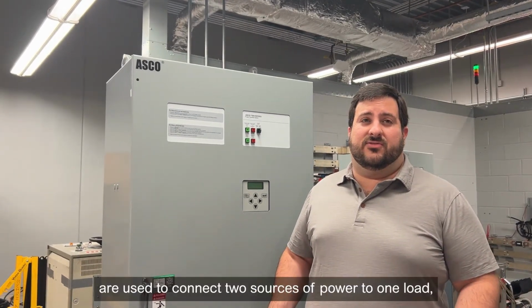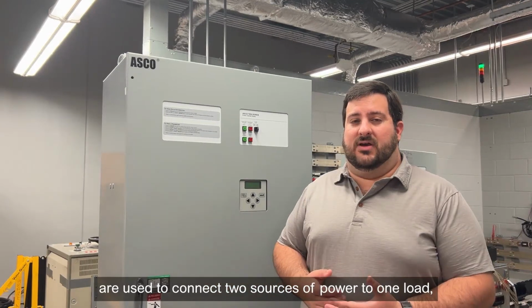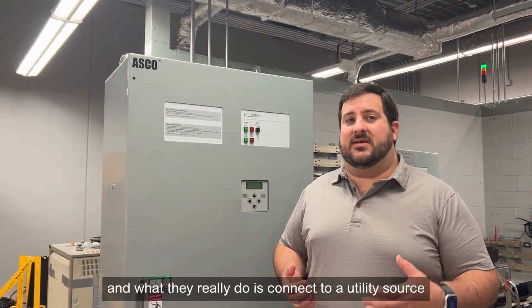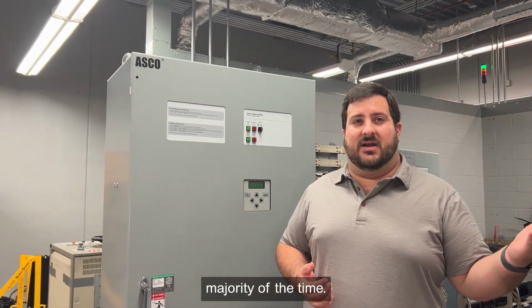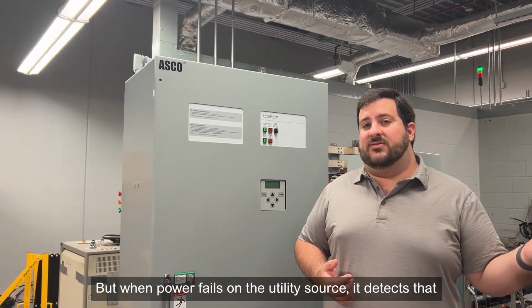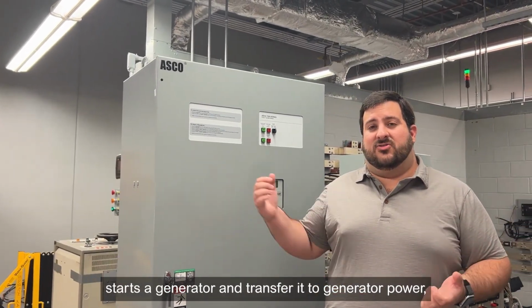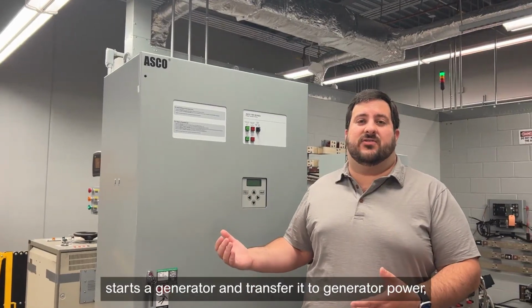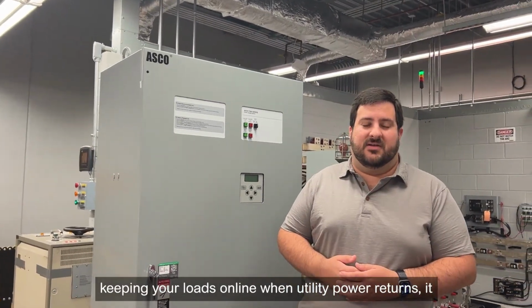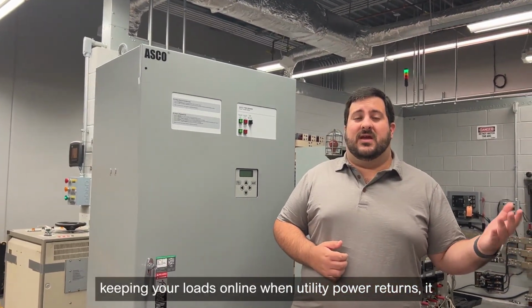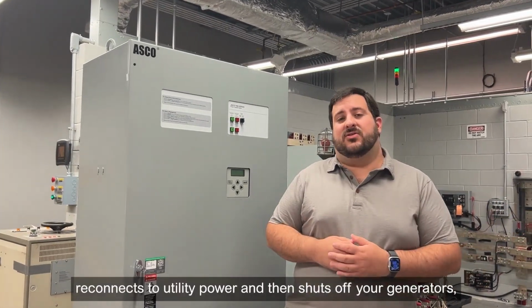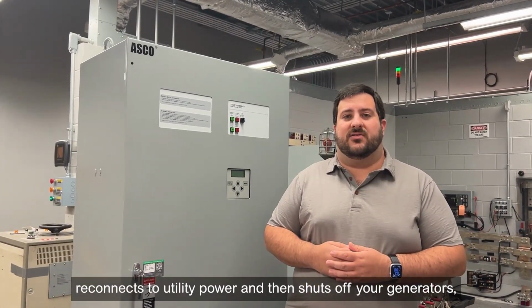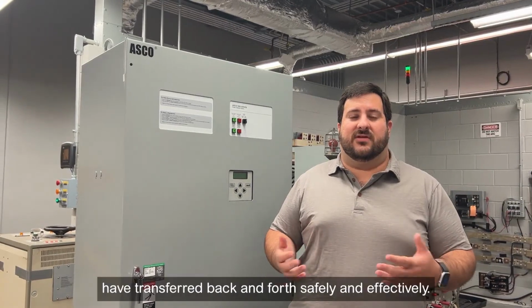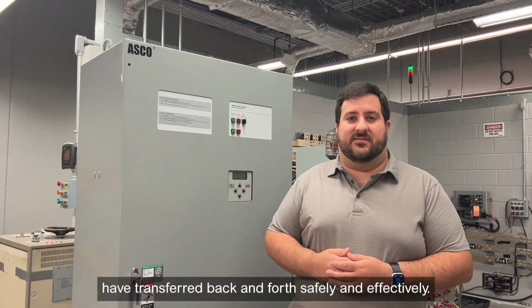Transfer switches are used to connect two sources of power to one load. And what they really do is connect to a utility source majority of the time, but when power fails on the utility source, it detects that, starts a generator, and transfers to generator power, keeping your loads online. When utility power returns, it detects that, reconnects to utility power, and then shuts off your generators, making sure that those loads have transferred back and forth safely and effectively.